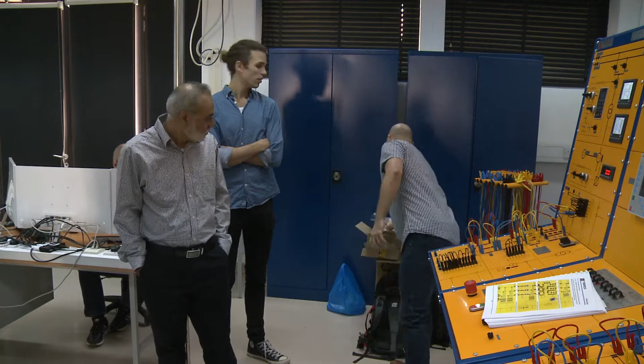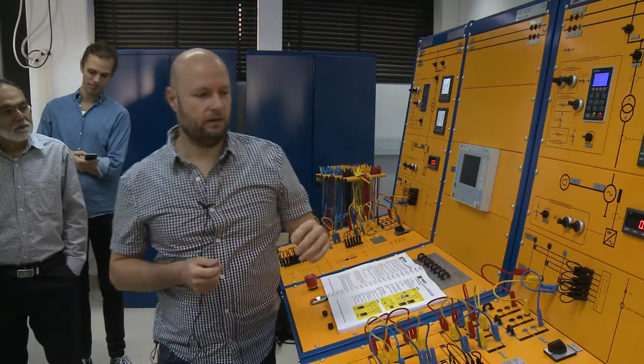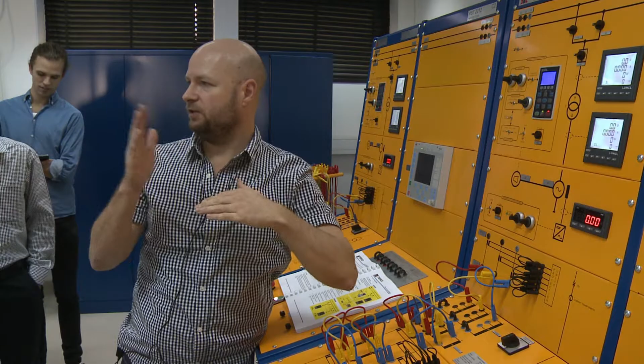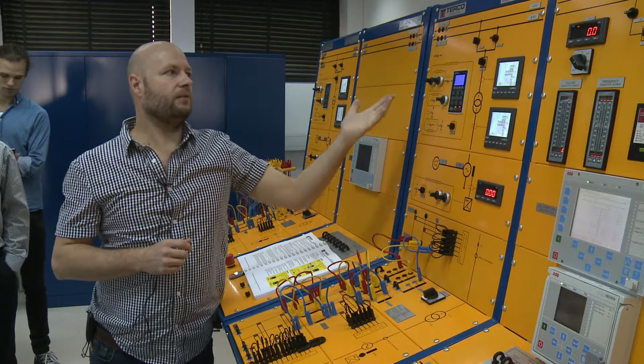I was going to mention something about the logical blocking. In the PLC, there is blocking to make sure we do the correct operations on the circuit breakers and the disconnectors or isolators. In real life, we're using CBs to make and break power connections, and isolators to route the power in different directions. First, when making connections, we must select which way we want the power to go, and then we connect the power. If we do that, that's fine.